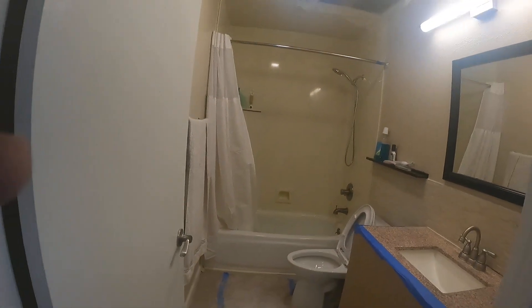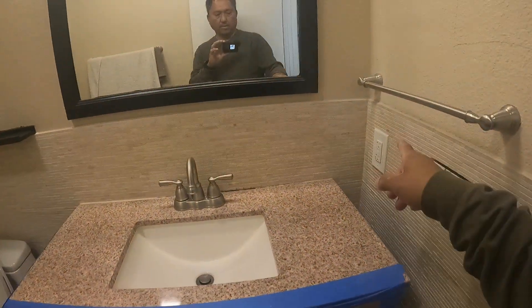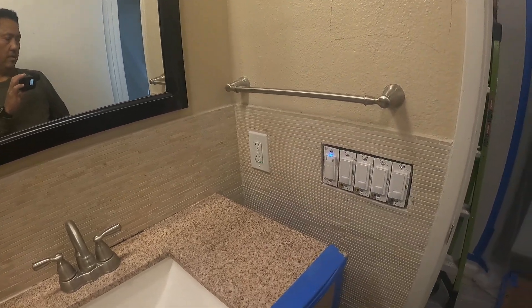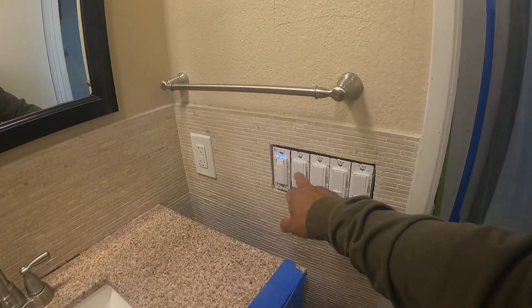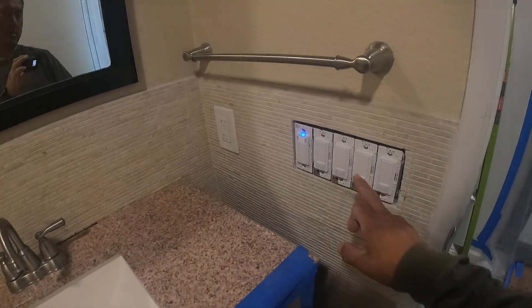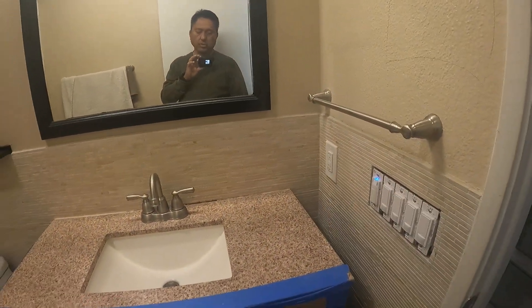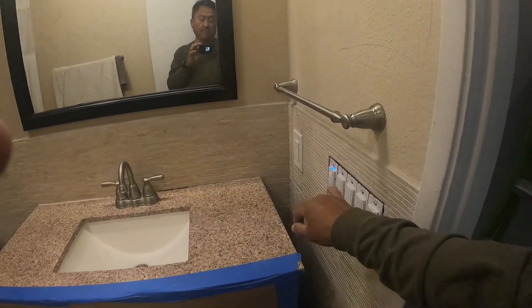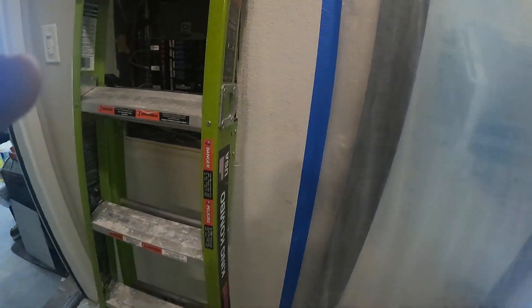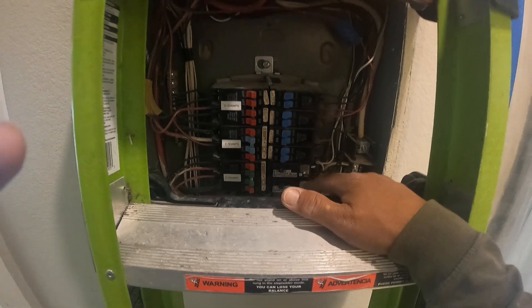The first hallway bathroom is done. We ended up running a new dedicated plug over here because the original electrician put in so many integrated plugs. We ended up putting a 5-gang box — that's how it's supposed to be for the original wall configuration. We added four switches: heater, fan, light, and nightlight. We ran a new dual breaker AFCI/GFCI.